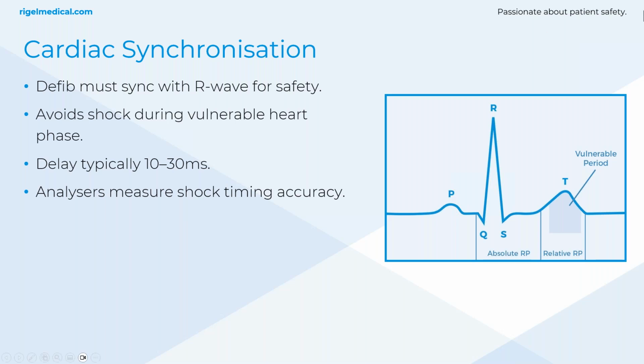So there's something called cardiac synchronization, and this is all to do with timing. Not all shocks are delivered in the same way. Sometimes with a rhythm like ventricular tachycardia that has a pulse, you don't just want to shock at a random point in time. You need to time it within the heart's natural rhythm. And this is where synchronized cardioversion comes in. What we're doing is aligning the shock with the R wave, and that's this spike here, represented on the ECG.